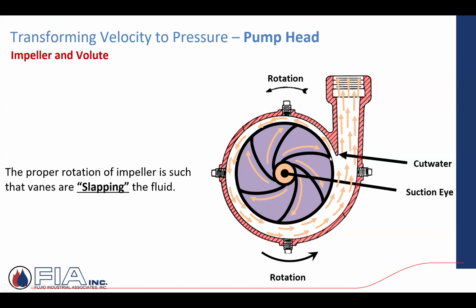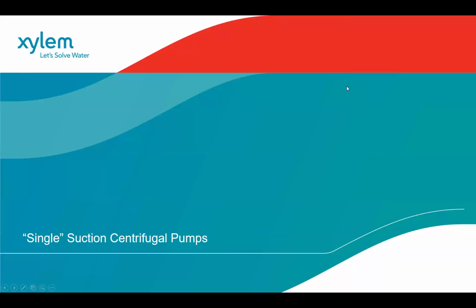One expression you'll hear sometimes from the field is, when the impeller is spinning in the proper direction, it's as if the vanes are slapping at the water. They're not scooping, they're slapping, because they're rotating, they're adding velocity. So as that water enters that eye and gets flung along these vanes into that volute, into that casting, it gets directed and discharged out the discharge nozzle.